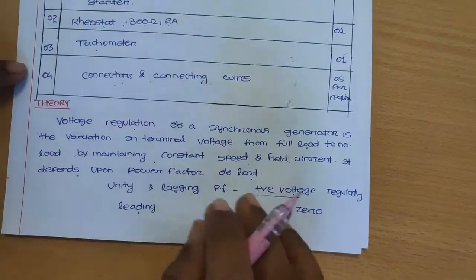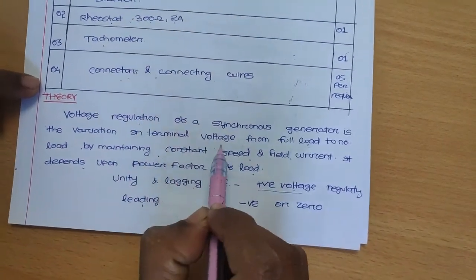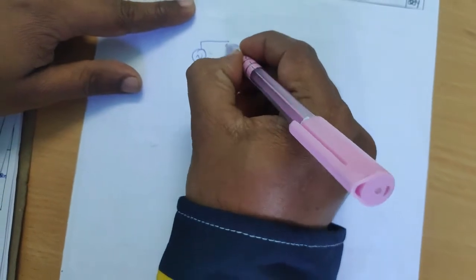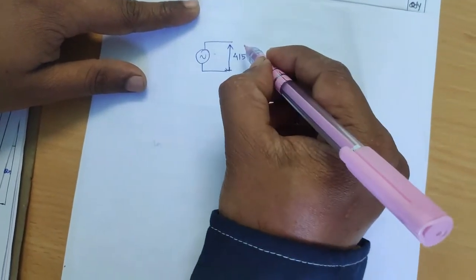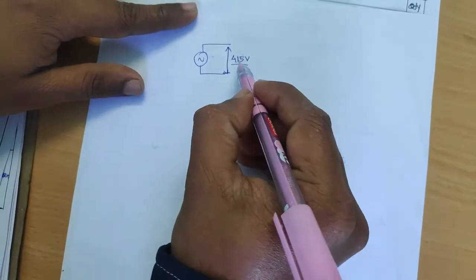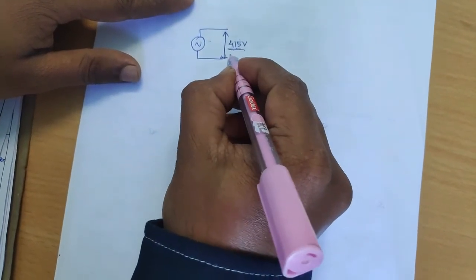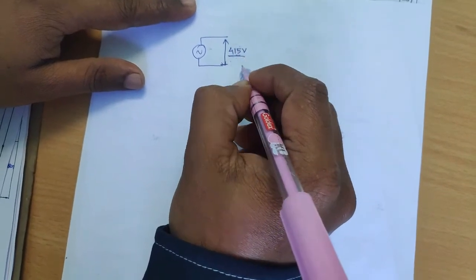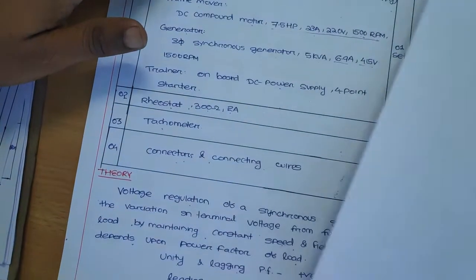Let's go into the theory in depth. First, you should know what the voltage regulation of a synchronous generator is. Voltage regulation of a synchronous generator is the variation in terminal voltage from full load to no load by maintaining constant speed and field current. Suppose rated voltage is 415 V when fully loaded — when this load is thrown off, the voltage will obviously increase or decrease depending upon the power factor. The no-load voltage is during the absence of load, and the rated voltage is during the presence of rated load condition at the output of the synchronous generator.